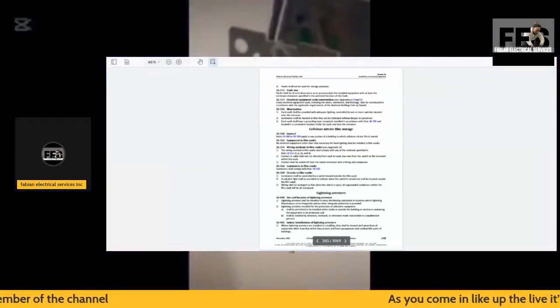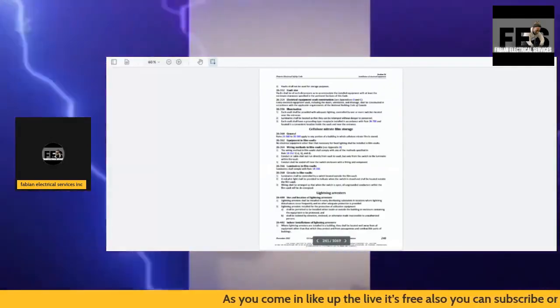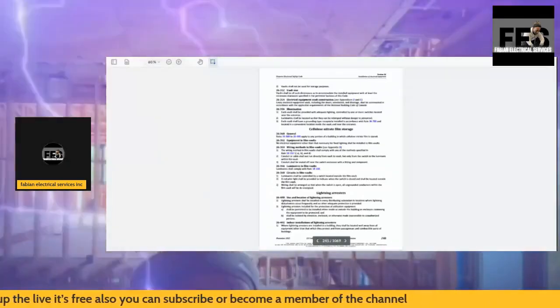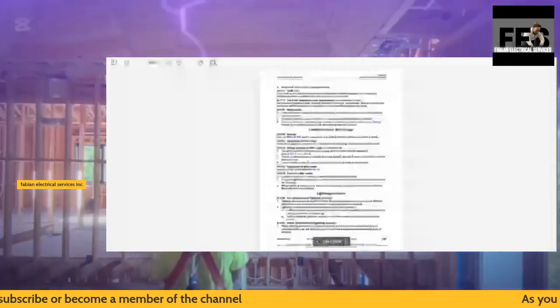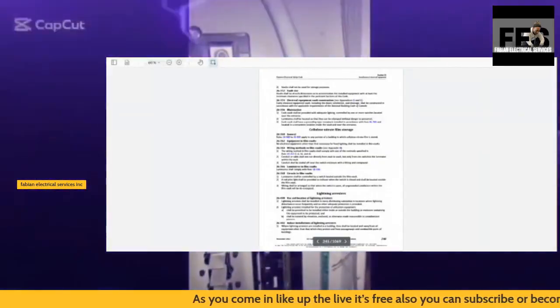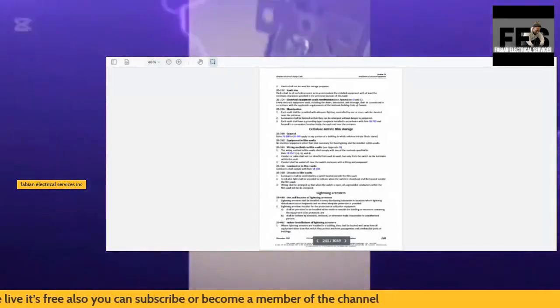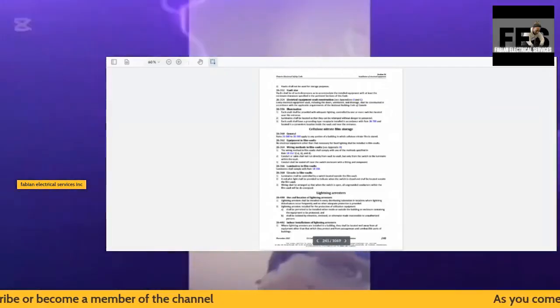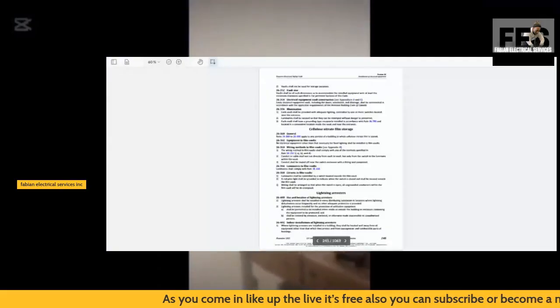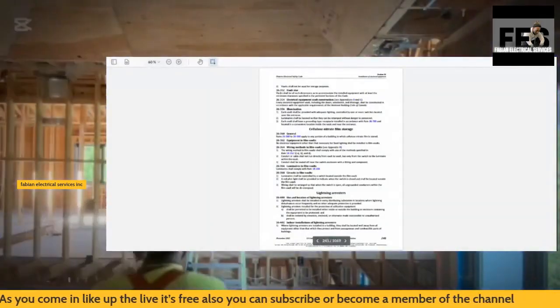Neutrals and grounds must be kept separate in the sub panel with the bonding strap between them removed. So again, you will also see that on some of my videos when it comes to the removal of the bonding strap. I have actually shown that on the channel itself. So for all those who have missed the previous live stream, you can go back and check out the previous live streams. You can also check out the previous videos and my shorts, and you will see the actual grounding and bonding strap that I had removed from a panel.